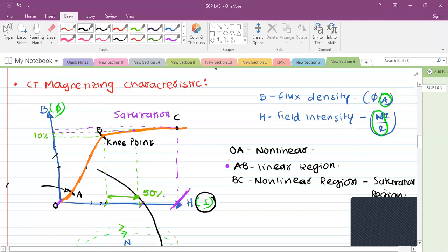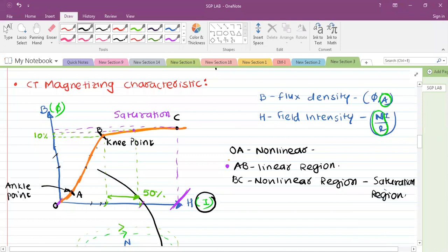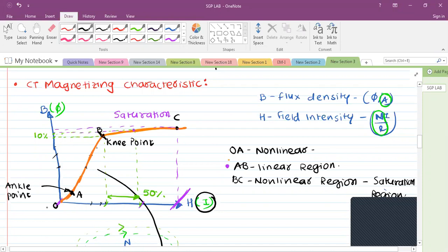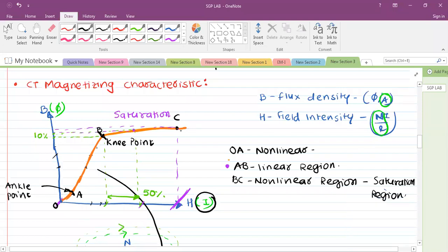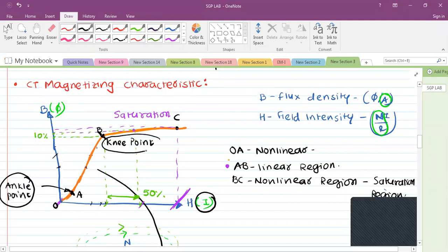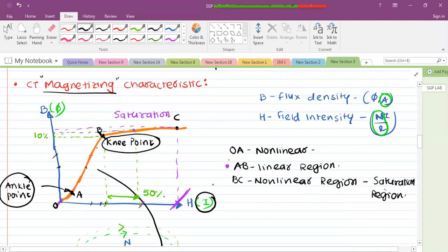So there are two points you can see on the characteristic. This is called the ankle point, and the other one is called the knee point. The region between the ankle point and the knee point is linear, and that is where the name comes from. If you look at it, just look at the leg. This is the knee point. This is our foot, this is the ankle point, and this looks like a leg. So the points on the characteristic are called the ankle point and the knee point. Clear on the magnetizing characteristic of any core? Understand?